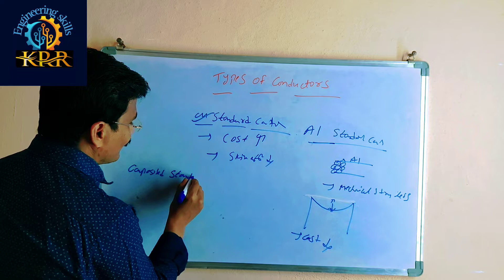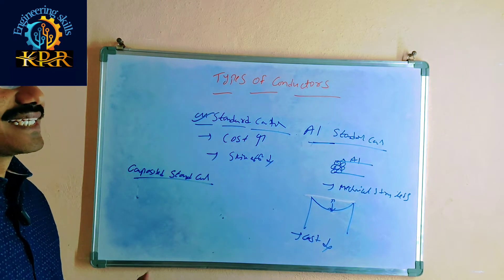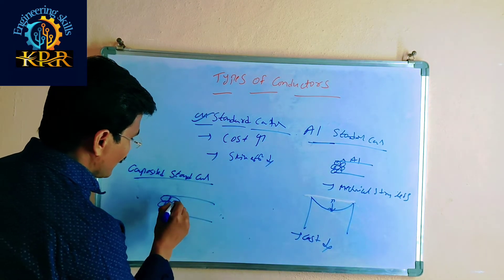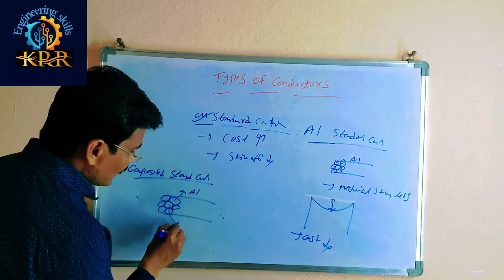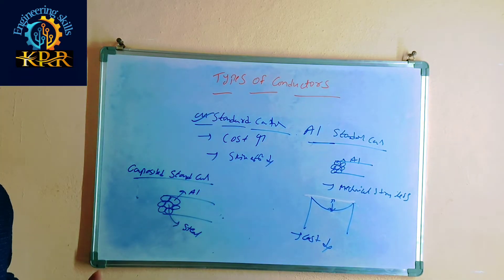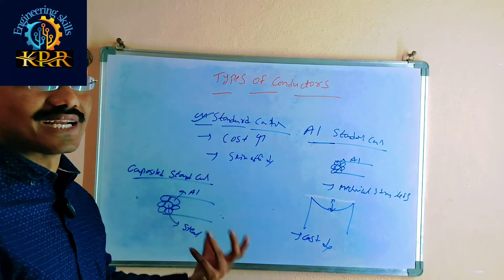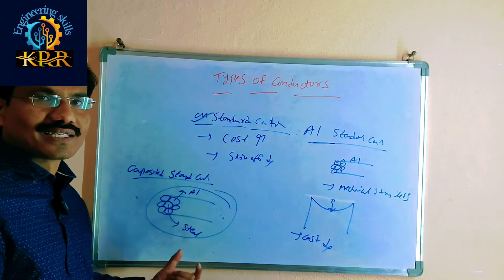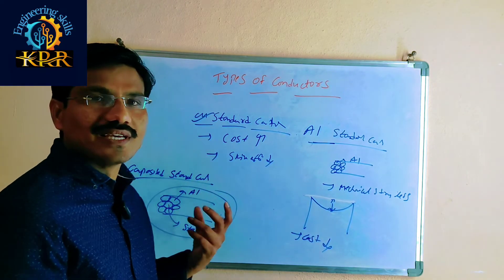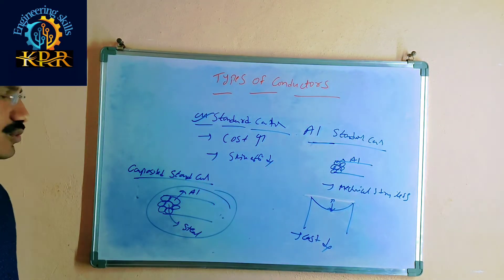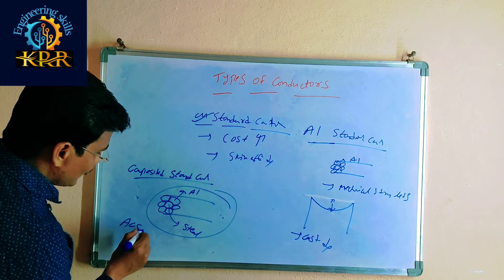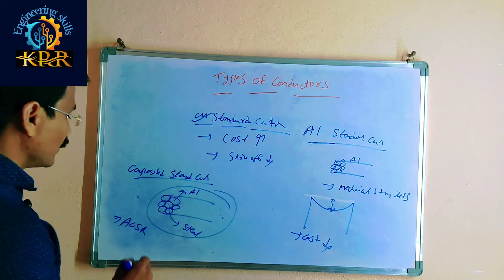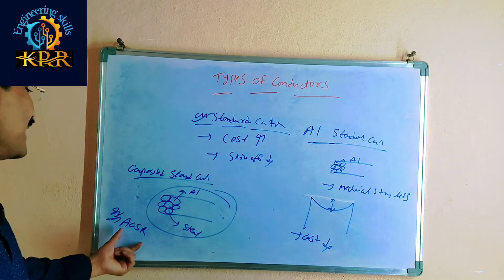In the composite stranded conductor, the outer strands are made with aluminum and the inner strands are made with steel. Aluminum has high conductivity, so the outer strands provide more conductivity. The inner steel strands provide more mechanical strength. Overall, the conductor has increased mechanical strength and increased conductivity. An example of this type is the ACSR conductor — Aluminum Conductor Steel Reinforced.